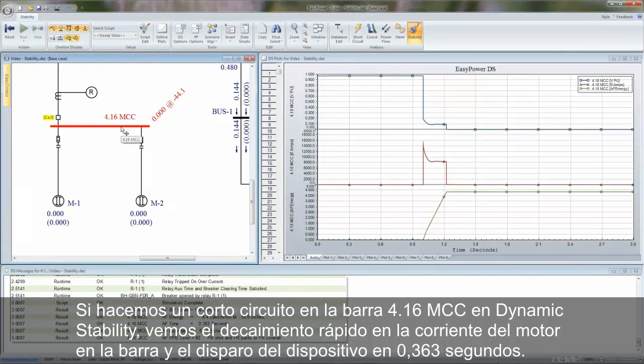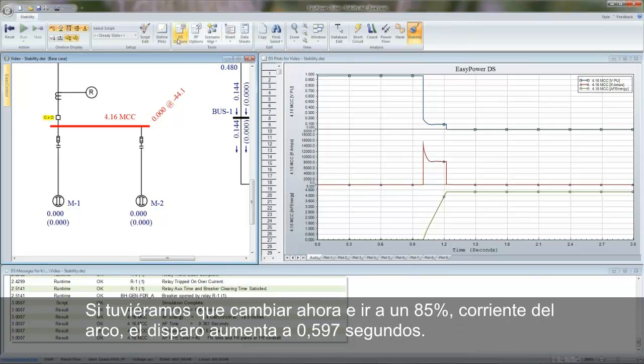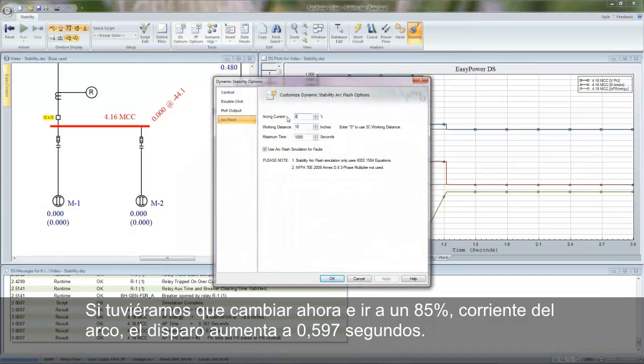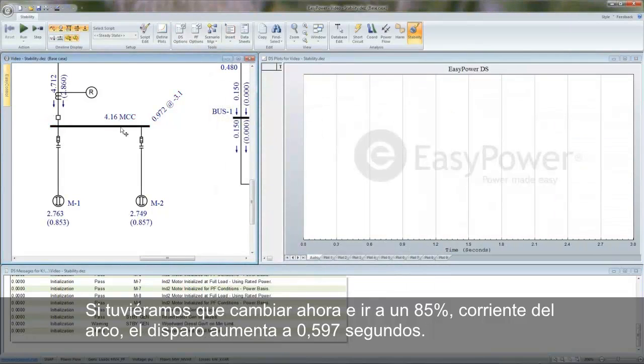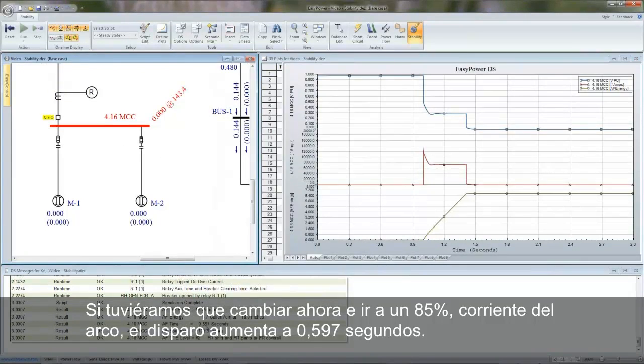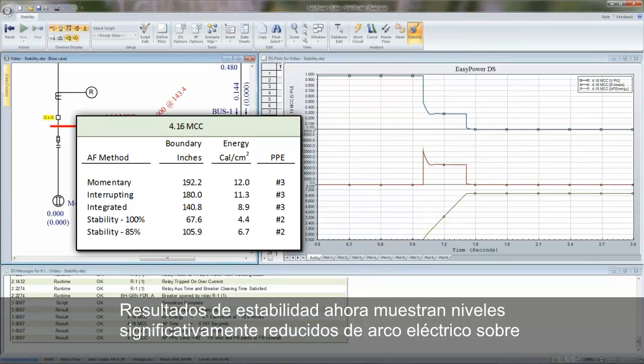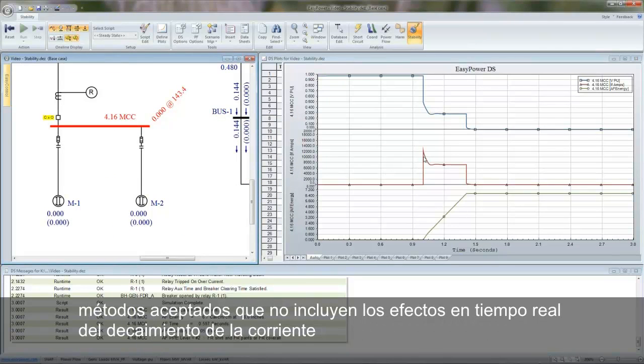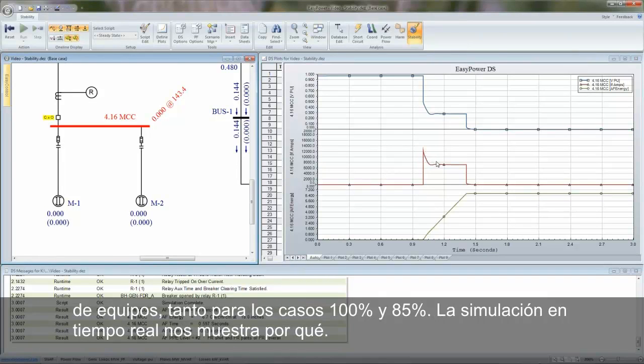If we fault bus 4.16 MCC in dynamic stability, we see the quick decay in motor current on the bus and device tripping in 0.363 seconds. If we were to now change and go to an 85% arcing current, the trip time increases to 0.597 seconds. Stability results here show significantly reduced arc flash levels over accepted methods that do not include the real-time current decay effects of equipment for both the 100% and 85% cases. The real-time simulations show us why.